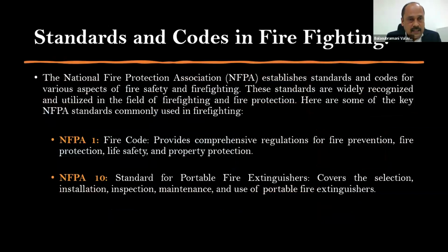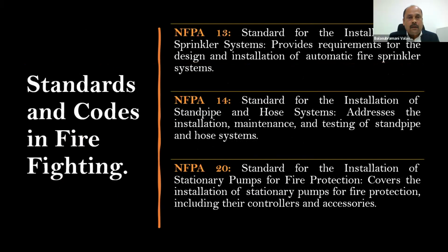There are numerous standards as far as NFPA and firefighting systems are concerned, not only firefighting but fire loss prevention, fire prevention, etc. We will be covering very few standards on this topic. NFPA 1 talks about comprehensive regulation of fire prevention, fire protection, life safety, and property protection. NFPA 10 talks about fire extinguishers. For sprinkler systems, NFPA 13. NFPA 14 for standpipe and hose systems. It addresses the installation, maintenance, and testing of complete standpipe and hose systems.